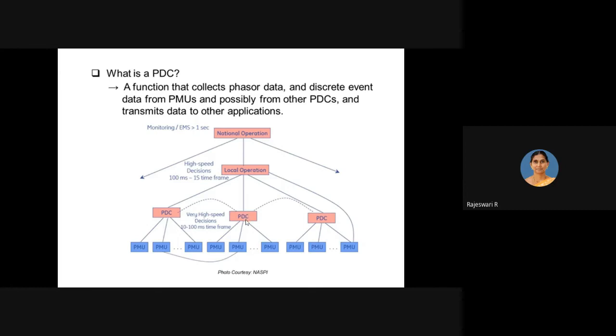Okay, so the data acquired at this PDC level can be used for making some local decisions, that is, to perform local protection at that particular substation level. That PDC acquired data can be used for that purpose, meaning it can be used locally. And then the collection of this phasor data is given to the next hierarchy, the super PDC. The super PDC may be at a regional load dispatch center. At the regional dispatch center level, there may be another PDC, which we call a super PDC, and that super PDC will be acquiring data from different PDCs.